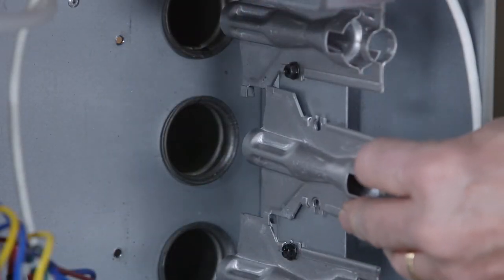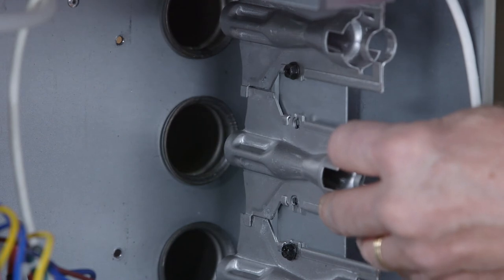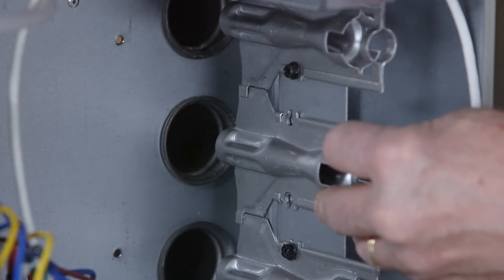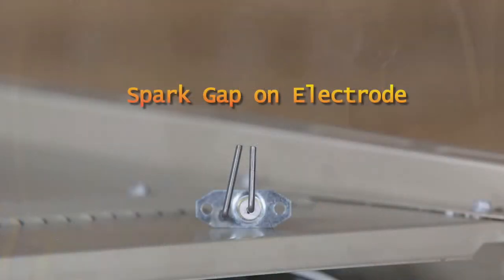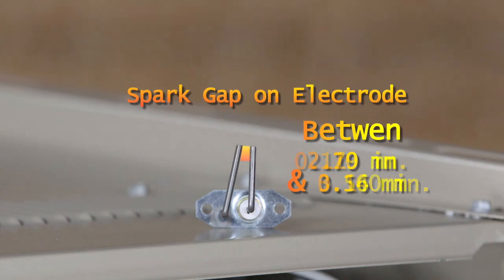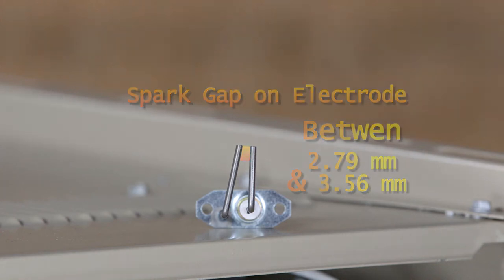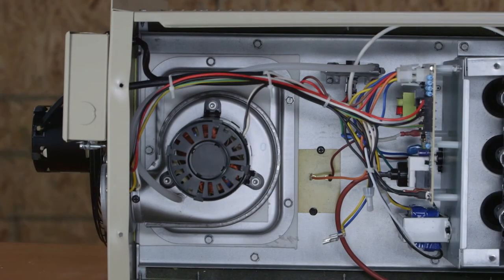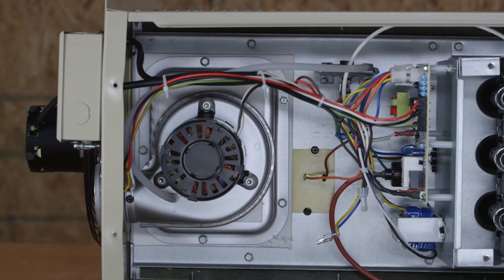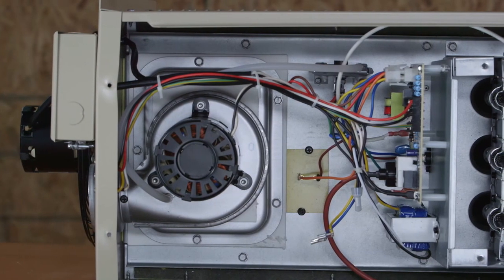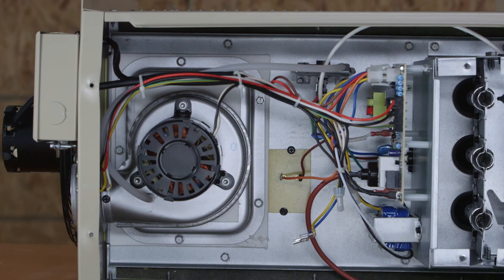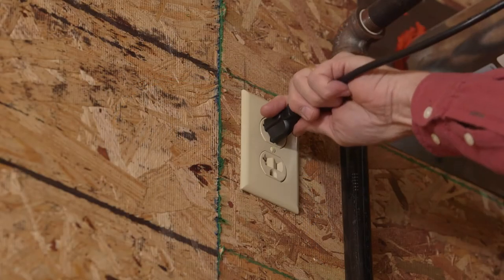When reinstalling the burner, be sure the heads line up properly to ensure flame crossover. Check spark gap on electrode and adjust if required. The gap should be between 0.110 inch and 0.14 inch, which is 2.79 millimeters to 3.56 millimeters. Use appropriately sized twist drills or feeler gauges to check the gap.